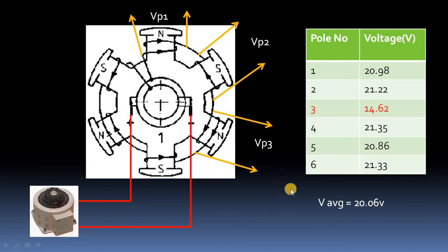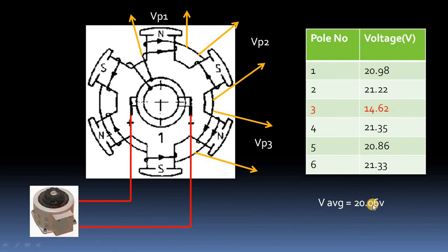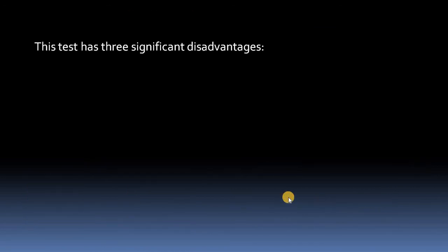For accuracy, we can calculate the deviation from the average value. If the deviation is greater than five percent, that pole has shorted turns. Deviation is calculated as the actual value minus the average value.